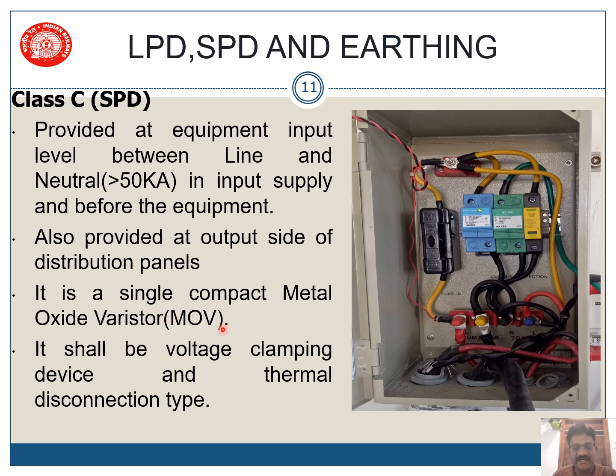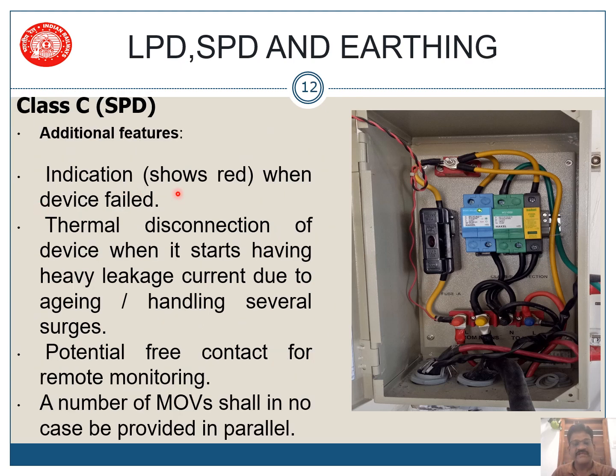It is generally a single compact metal oxide varistor. It shall be a voltage clamping device and thermal disconnection type. It also shows a red indication whenever there is a failure. The thermal disconnection device acts when it starts having leakage current due to aging or handling several surges. So whenever there is a heavy strike regularly, this can get damaged and a red indication will come. So you need to replace this when there are heavy lightnings regularly after some time. It is also provided with a potential free contact for remote monitoring, and a number of MOVs shall never be connected in parallel. एक ही MOV, बहुत ज़्यादा MOVs connect नहीं करना चाहिए in parallel.